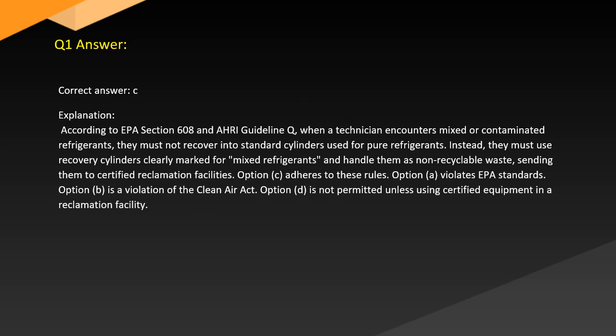Answer. Correct answer: C. Explanation. According to EPA Section 608 and AHRI Guideline Q, when a technician encounters mixed or contaminated refrigerants, they must not recover into standard cylinders used for pure refrigerants. Instead, they must use recovery cylinders clearly marked for mixed refrigerants and handle them as non-recyclable waste, sending them to certified reclamation facilities. Option C adheres to these rules. Option A violates EPA standards. Option B is a violation of the Clean Air Act. Option D is not permitted unless using certified equipment in a reclamation facility.